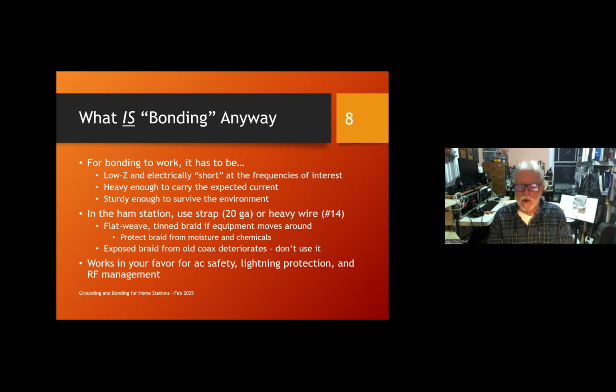If you've got to move your equipment around, you might use flat weave silver-tinned braid. You see that in automotive and equipment installations where there's vibration or equipment that has to move. It's okay to use that kind of braid, but you've got to protect it from moisture and chemicals - it has to remain dry. If water or chemicals get in there, it starts to corrode.